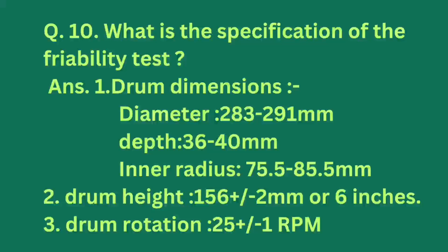Next question: What are the specifications of the friability test? Answer: Drum dimensions diameter is 283 to 291 mm, depth is 36 to 40 mm, inner radius is 75.5 to 85.5 mm, drum height is 156 plus or minus 2 mm, and drum rotation is 25 plus or minus 1 RPM.